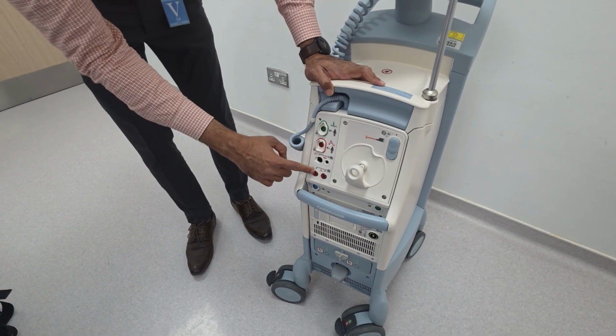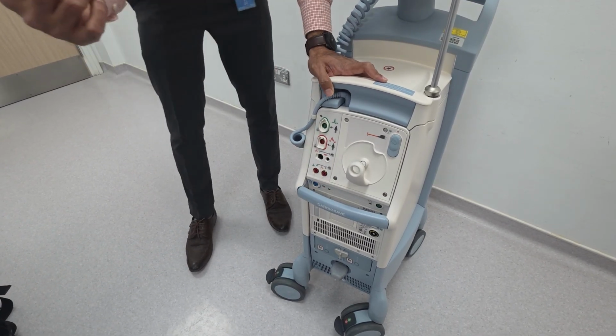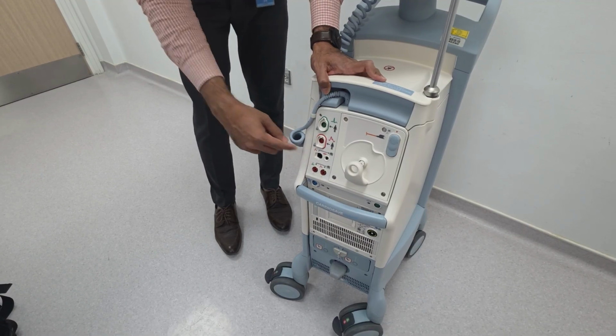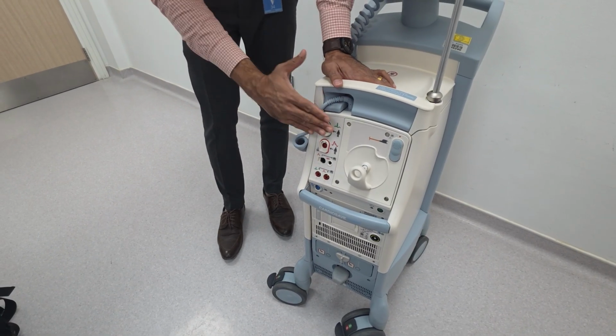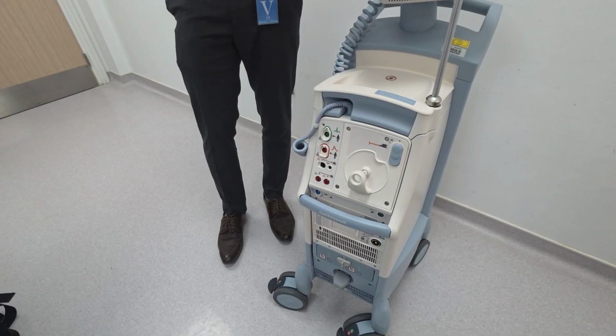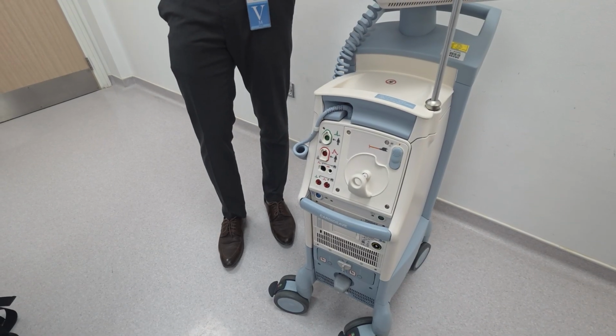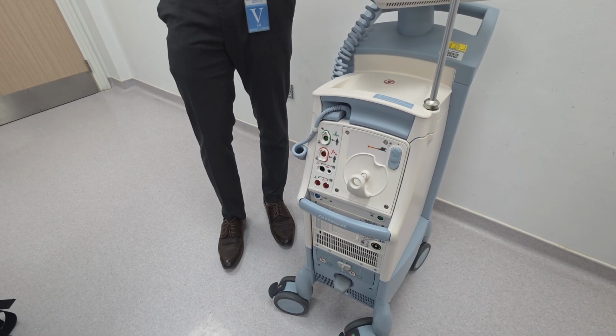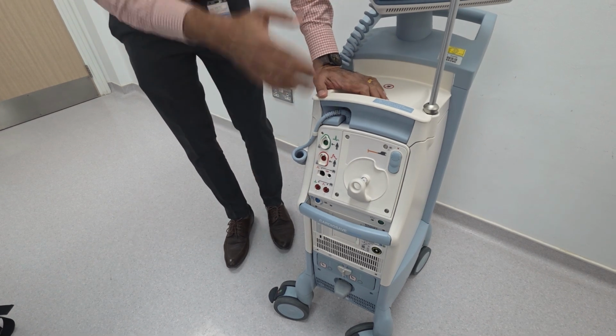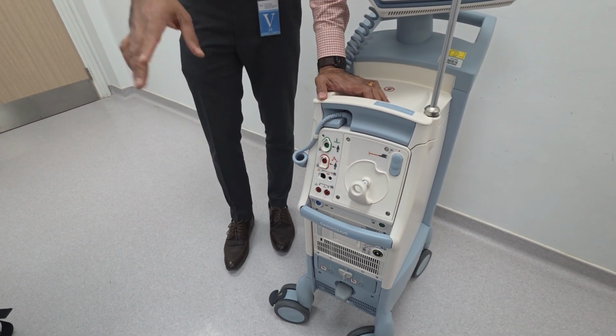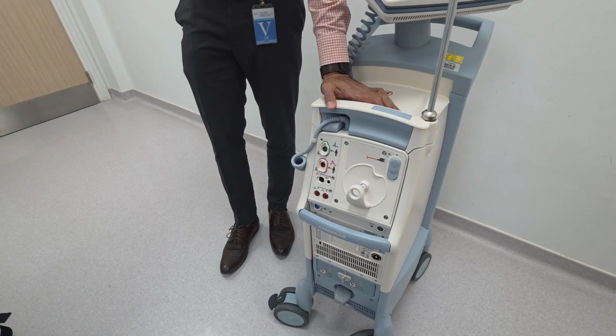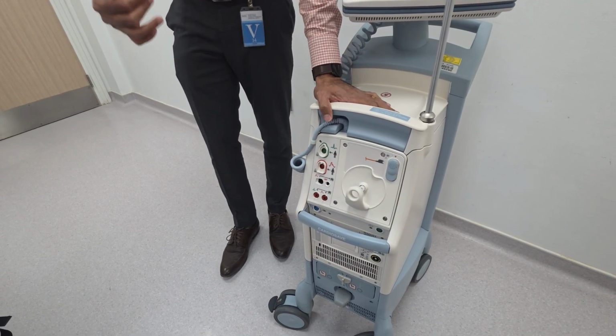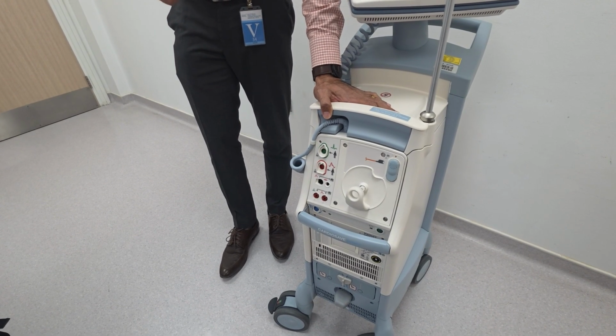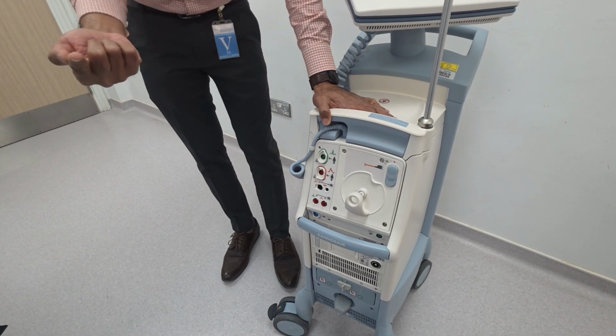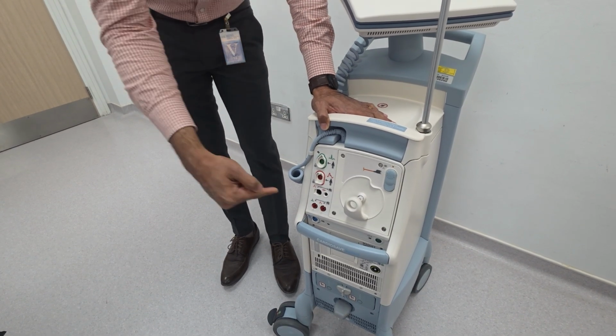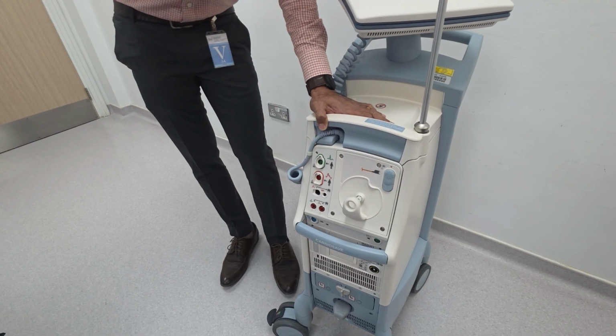And here, if you are using the external monitor cable connections, again marked here, you can take external monitor ECG, then you don't need this. If your patient is already hooked up with the external monitor ECG, then you don't need to have additional ECG connections. Take the slave, connect here, it will come. But that is different, no? It will not fix it for this, right? You should have this, I guess. Otherwise, we are giving a cable. We'll provide, whichever monitor you have, Philips or... Yeah, we have Philips. Yeah, it's a simple mono jack cable. Connect to the Philips and connect here. Nothing to do, ECG will come automatically.